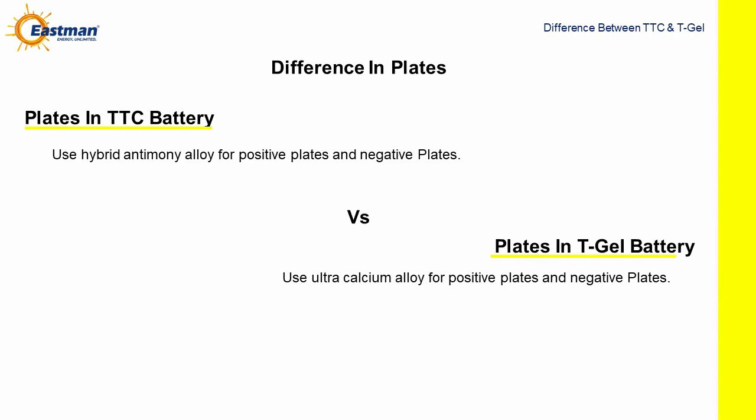Difference in plates. TTC battery uses hybrid antimony alloy for positive plates and negative plates. Whereas T-Gel battery uses ultra-calcium alloy for positive plates and negative plates.